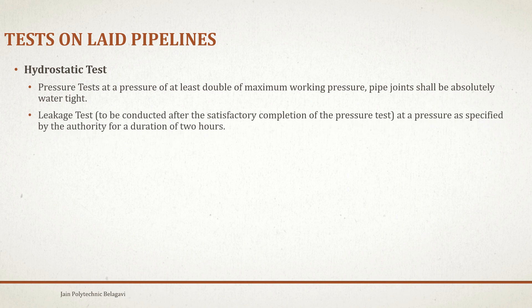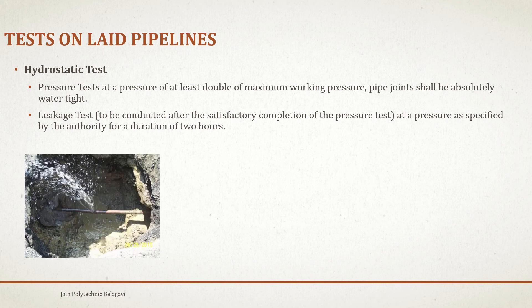There is a hydrostatic pressure test conducted at a pressure of at least double the maximum working pressure. Pipe joints shall be absolutely watertight. A leakage test is to be conducted after satisfactory completion of the pressure test, at a pressure as specified by the authority, for a duration of two hours.